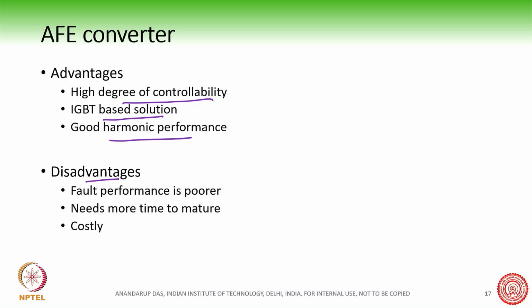What is the disadvantage? Fault performance is poorer. Remember, 2000 or 2500 amperes of current are flowing, and the short circuit withstand capability of the thyristor is much more than an IGBT or a MOSFET. So during a fault you have to quickly turn off the devices, otherwise it will be destroyed.